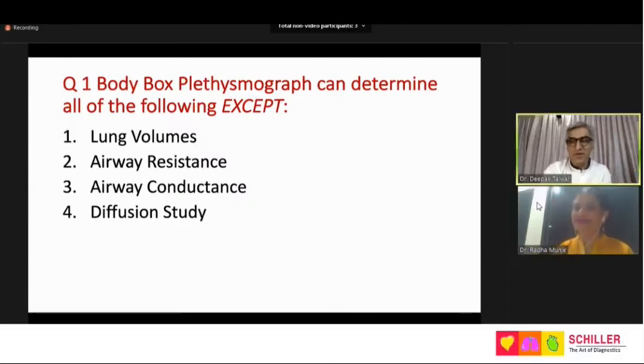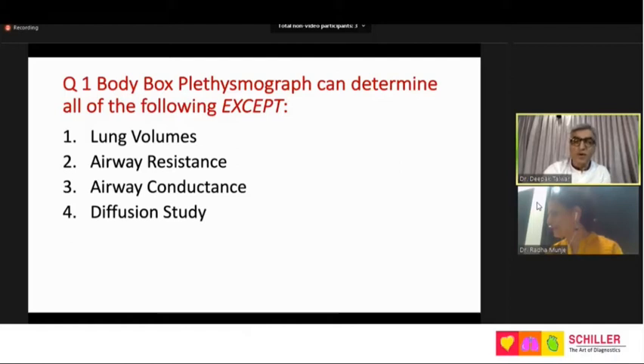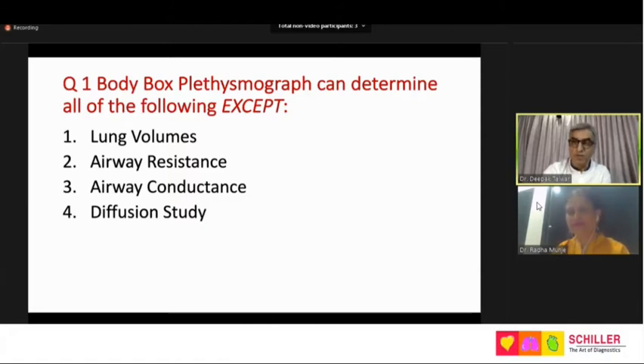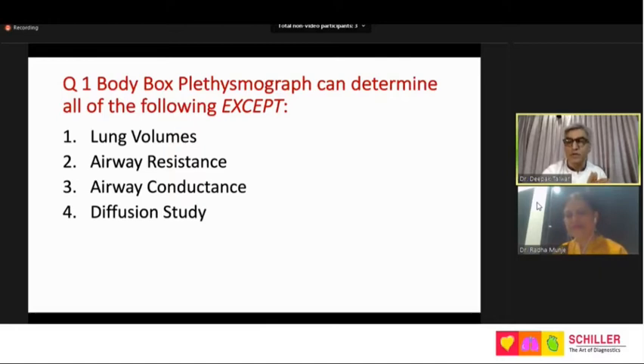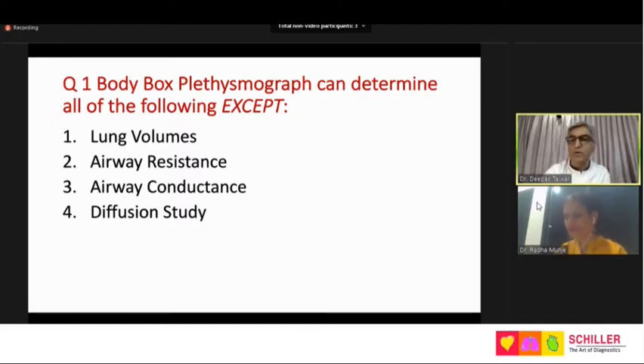Over to Dr. Talwar. It is a wonderful response that at least 50 percent know that diffusion is not part of body box. Primarily, body box was first considered for compliance studies, since lung volumes were being done by helium dilution or nitrogen washout methods. When the body box came, we started thinking about lung compliance and airway resistance — SRaw and GAW. These are terminologies rarely used in clinical practice. In clinical practice the body box is used for lung volumes, but it can also determine airway resistance and conductance — SRaw and GAW come as a byproduct for all cases. For diffusion study, you need a separate apparatus and diffusion gas; it is not part and parcel of the body box.